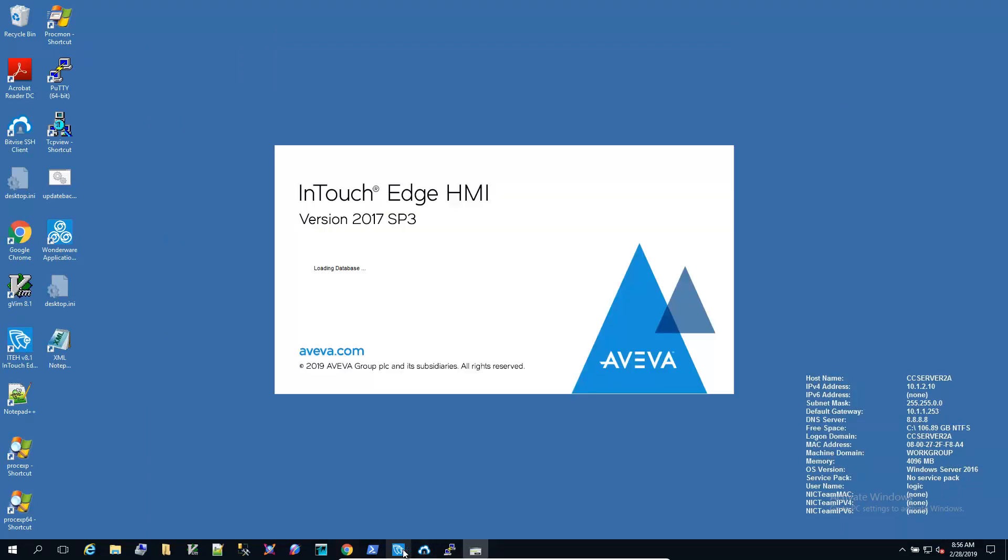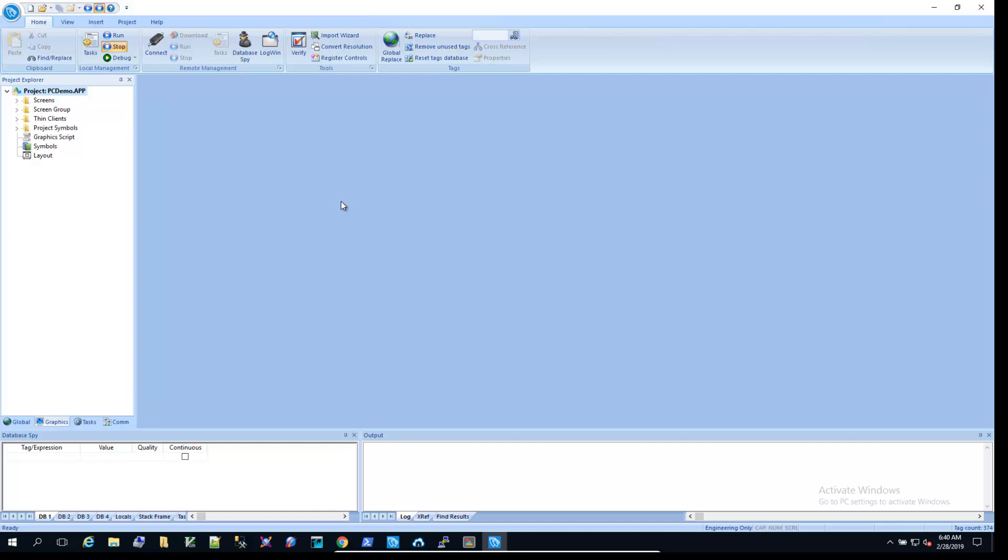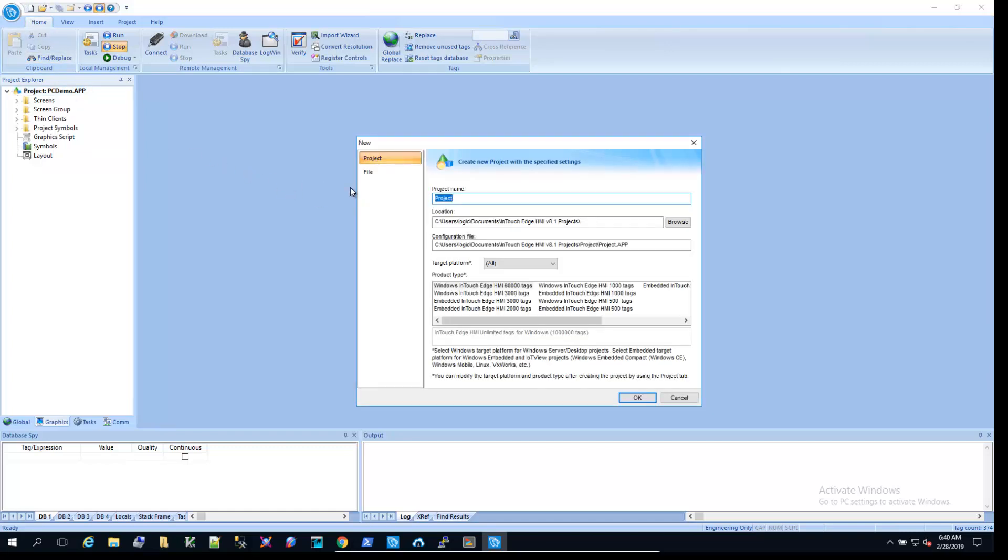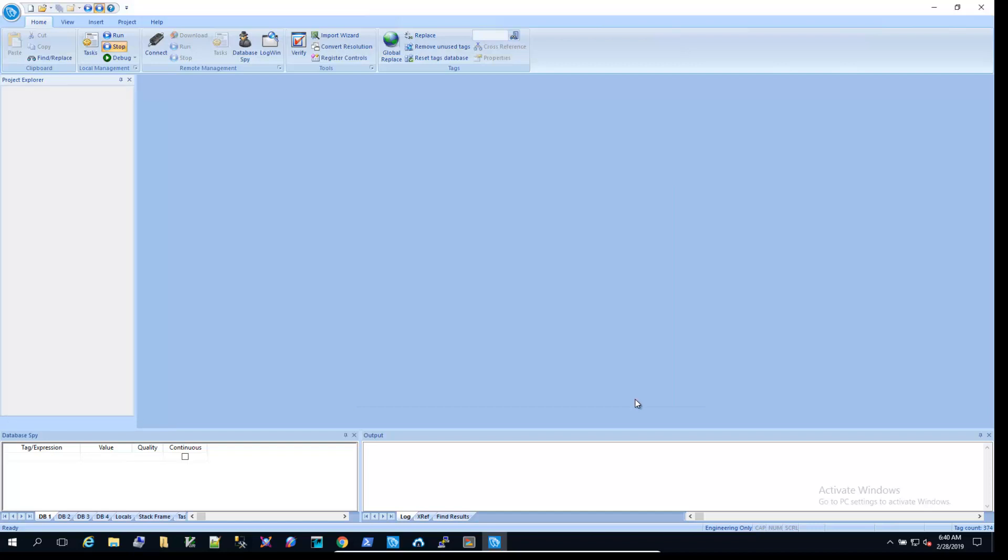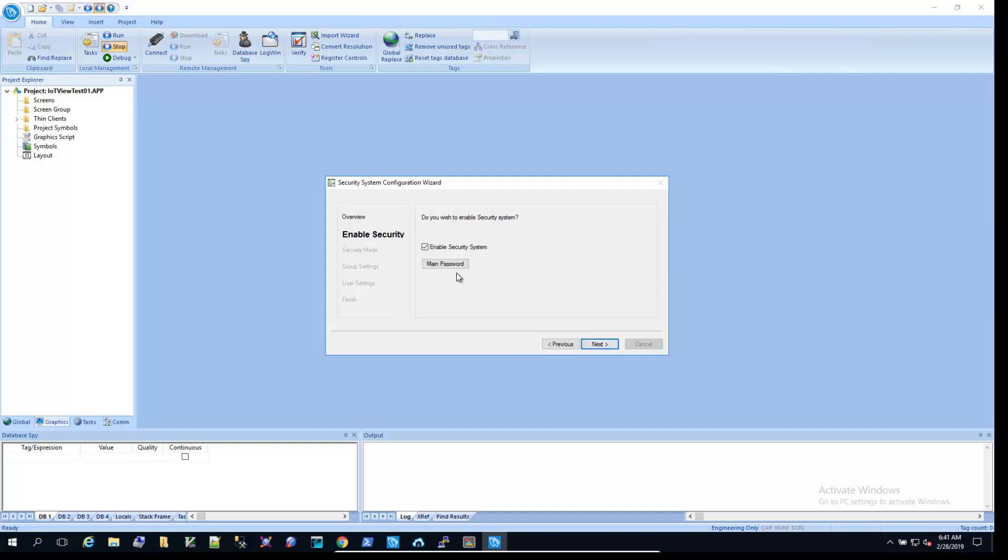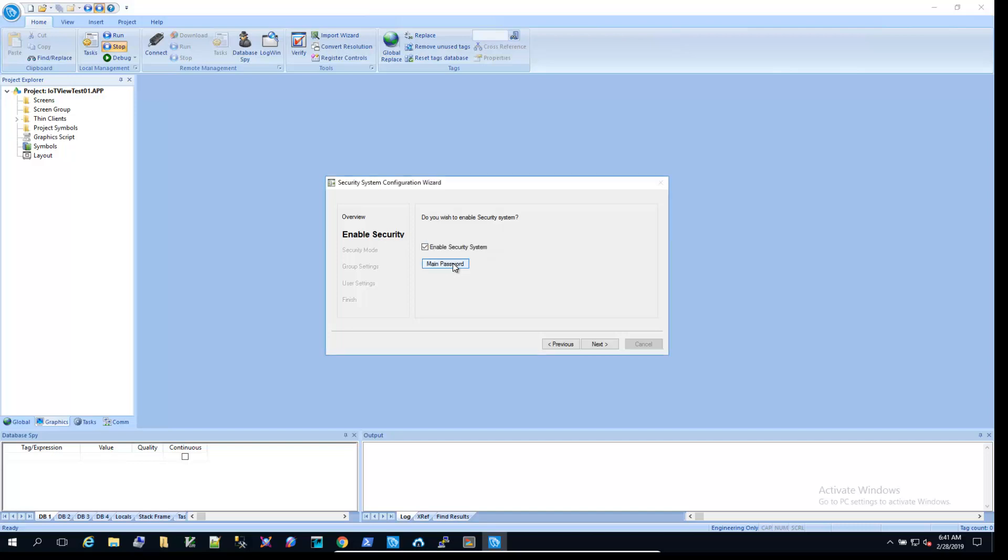So now let's run InTouch Edge HMI. Now we're in InTouch Edge. I'm going to go ahead and create a new project. We want to select the target to be an embedded InTouch Edge HMI. This is going to be a pretty small project, so I'll just select the 500 tag embedded project. It's asking me for the security wizard, so I'll go ahead and create some logins. For IoT view, the only security mode available is local only, so you want to make sure that this is selected.